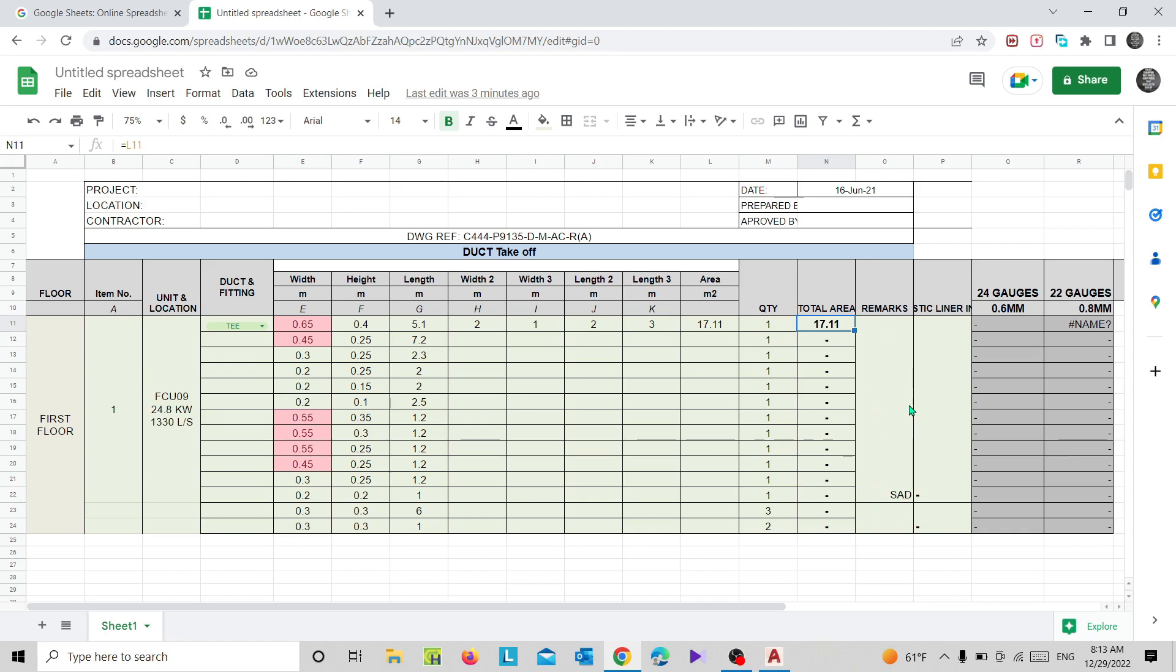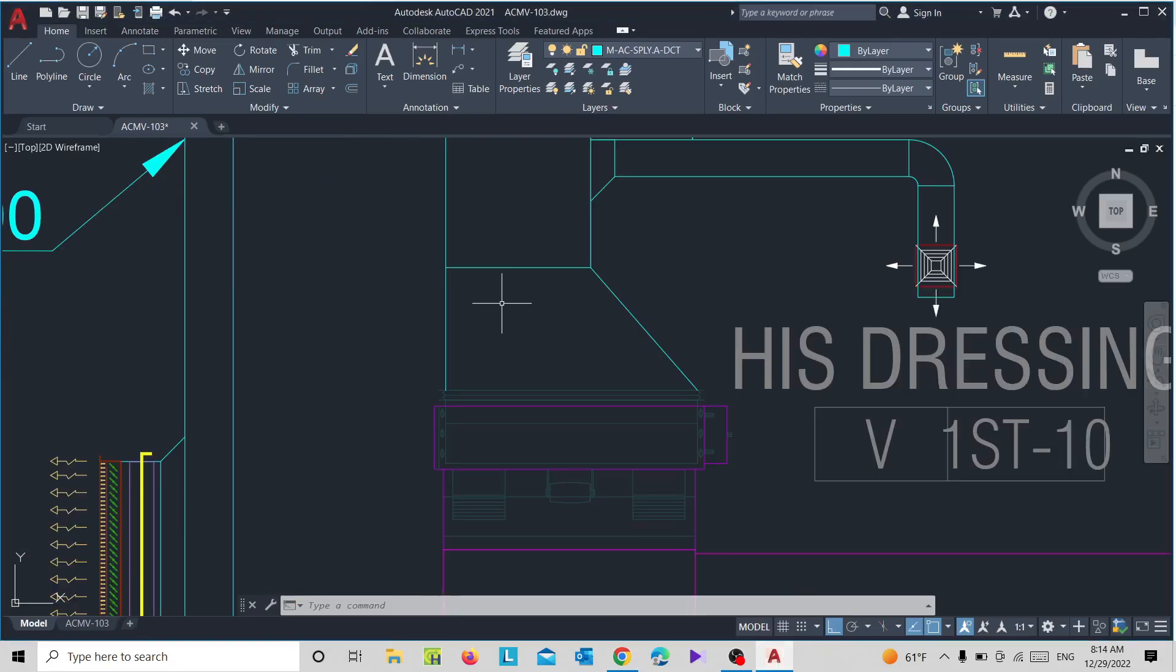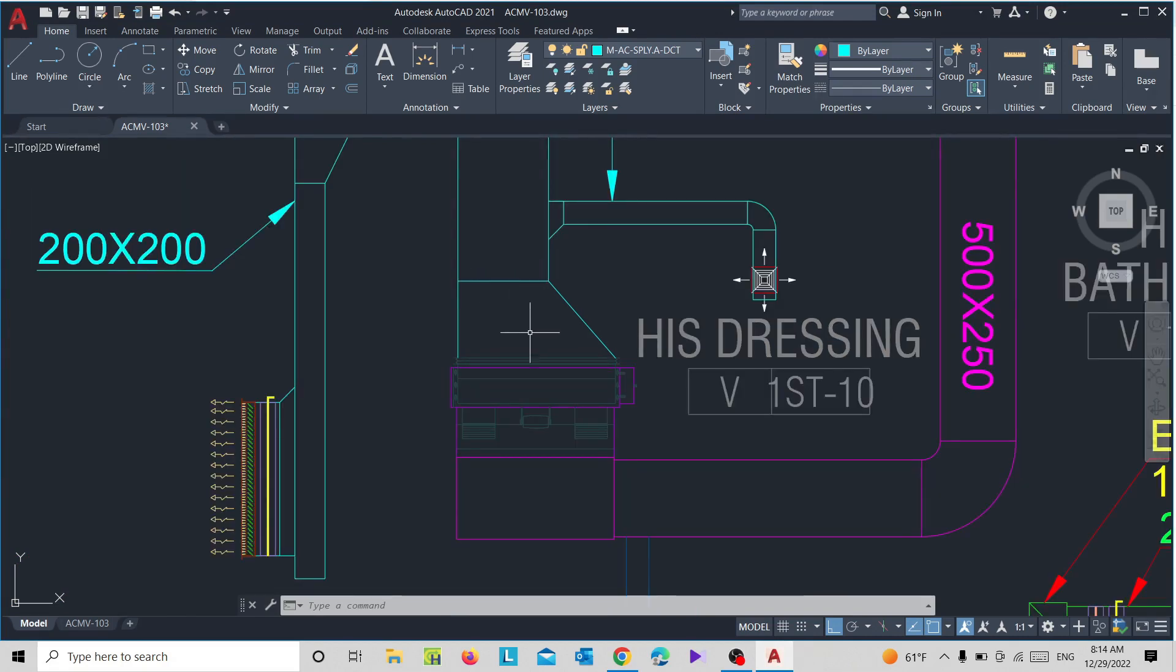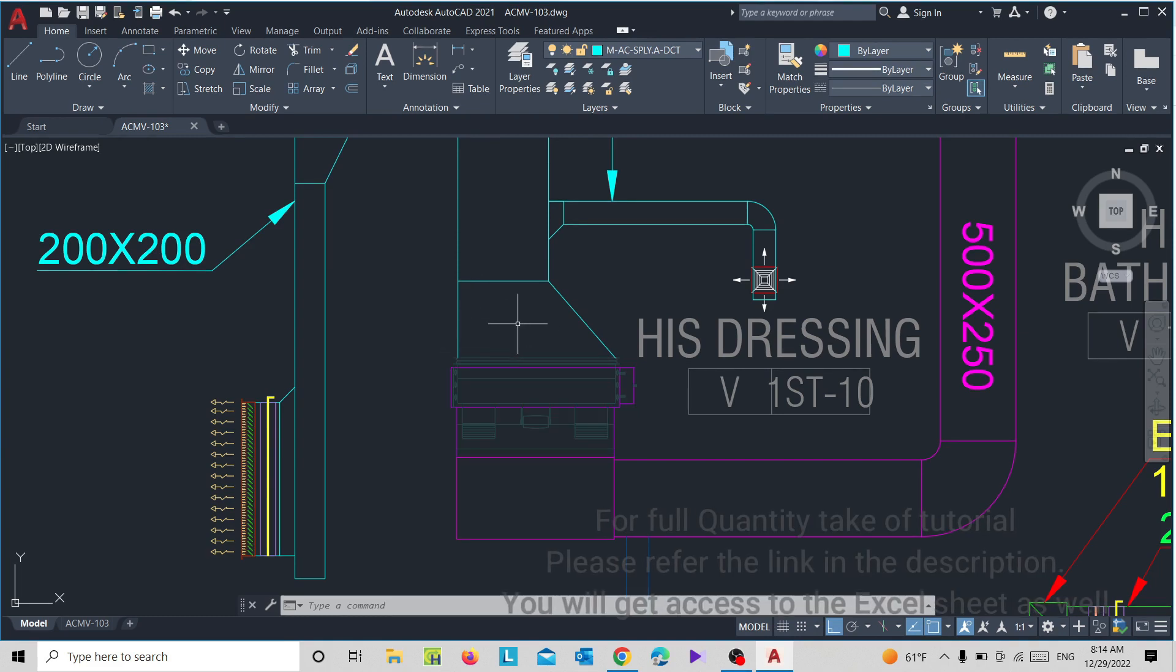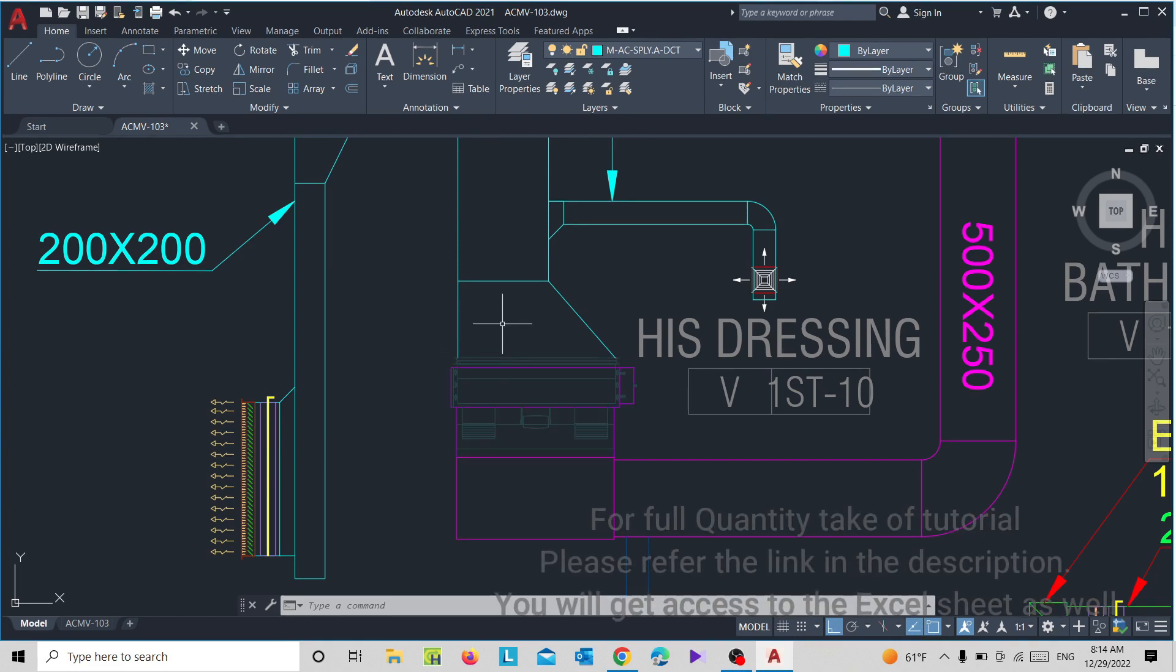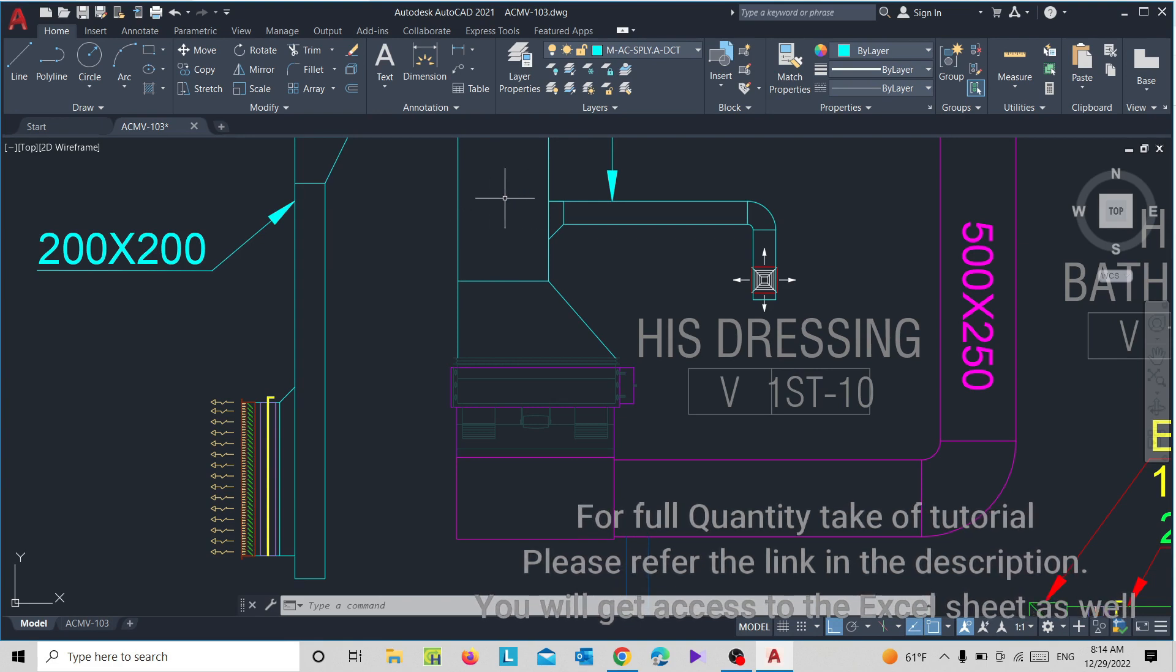Acoustic liner - what is the advantage of this acoustic liner? Well, acoustic liners will be useful for noise depression. It could be a replacement for the sound attenuator. Mostly when it comes to FCUs, this FCU hookup area will have this acoustic liner. For the FCU, the length of the acoustic liner should be at least 1.5 meters from the FCU.